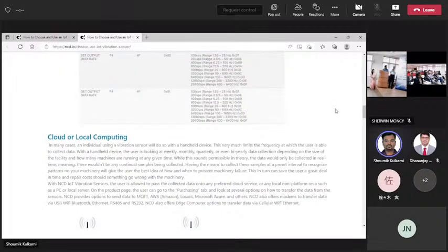It says to do it once an hour, and then it sends and stops, and again it sends. You can send once in an hour, or once in 4 hours. Once in 4 hours can give you 8 years of battery life. The embedded battery can last 8 years, a very long time, with this kind of signal going in one shot and then waiting for 4 hours. If you want it every 1 hour, you can, but then the battery life changes. For 2 years of battery life, you can keep sending this kind of signal every 2 minutes. So that is the kind of level that it has. Thank you very much.